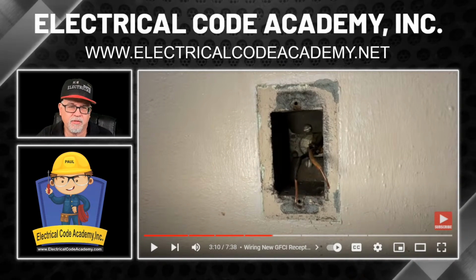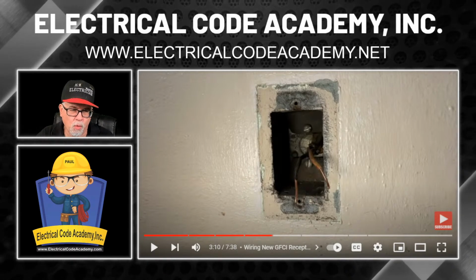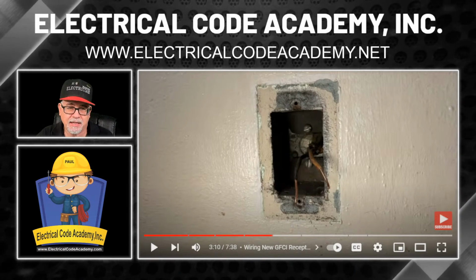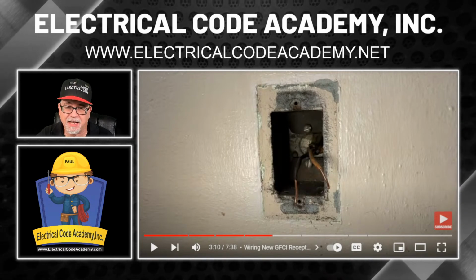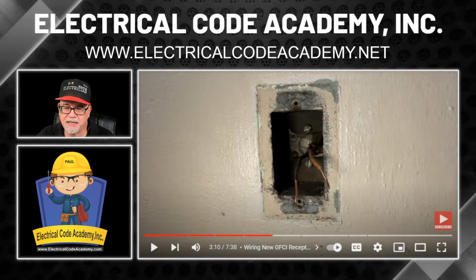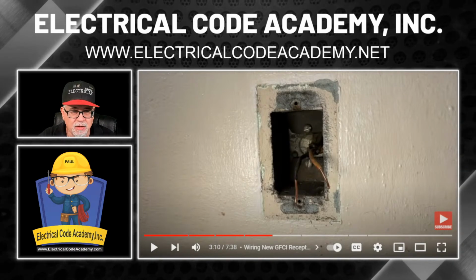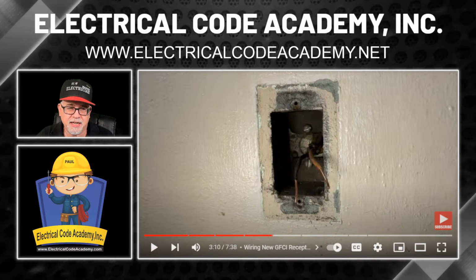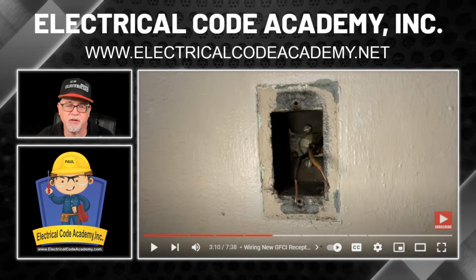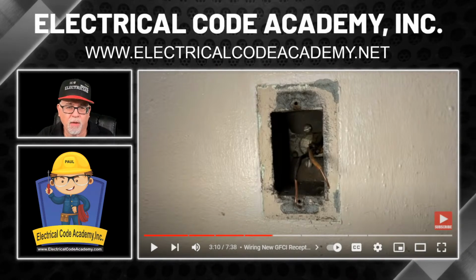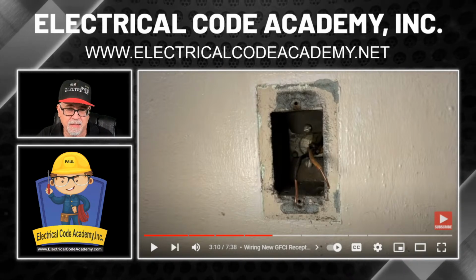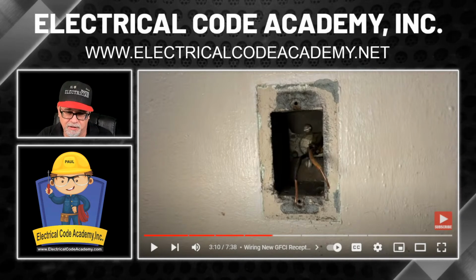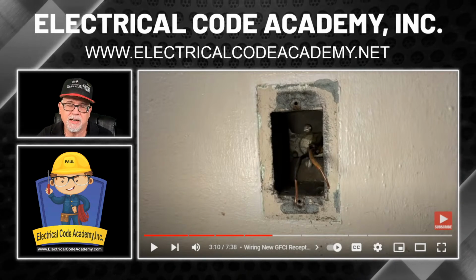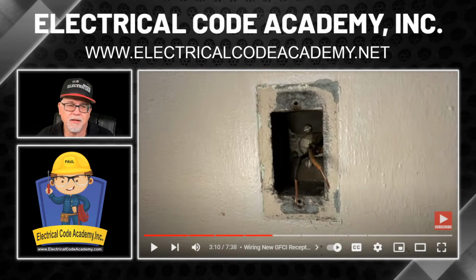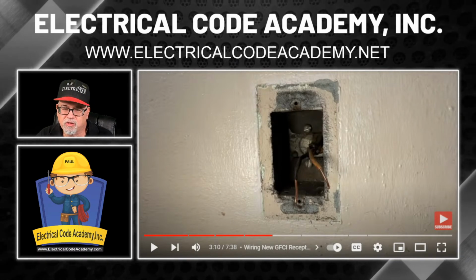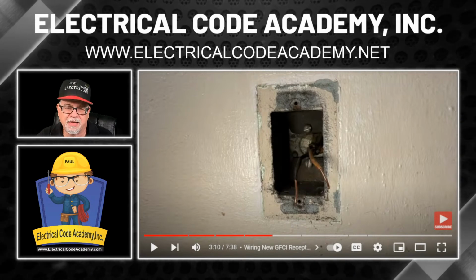And I'll say cable because this is a metal box, so the chances are that is old BX cable back in that wall. Remember, BX is not the same as AC cable, and it's certainly not the same as MC cable. BX was an experimental GE product from years ago. It's been used a lot in older homes. The armor on the old BX is not the same as AC cable. It's not an equipment grounded conductor. If it was, then this wouldn't be 2-wire, right? The BX predates when the equipment grounds were required. So just because it's metal, don't think you can use that as an equipment ground.